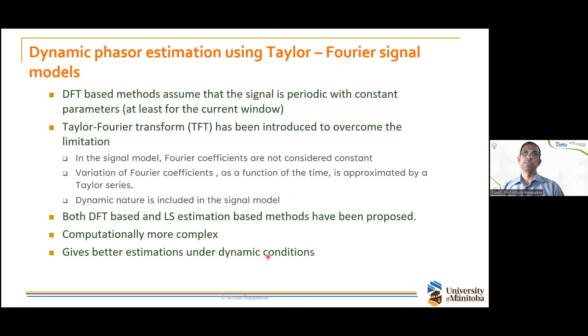There are different methods as we discussed, like the DFT method, and you can use wavelet-based transforms to do that. Optimization is basically the least square methods, and there are also Taylor Fourier transform based methods. Each has advantages and disadvantages, so I won't go into detail due to time. Typically, DFT works quite well because it's easy to compute and has good harmonic rejection. The only problem is spectral leakage at off-nominal frequencies.